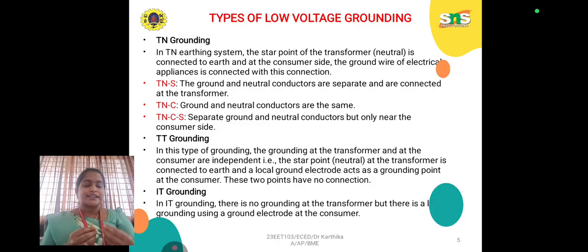Here TNS means the ground and neutral conductors are separate and are connected at the transformer side. TNC means ground and neutral conductors are the same. TNCS means separate ground and neutral conductors but only near the customer side, which means our house side. In TT grounding, the grounding at the transformer and at the consumer side are independent, like the star point. These two points have no connection. And in IT grounding, there is no grounding at the transformer, but there is a grounding connection using a ground electrode at the consumer point. Mainly three types of low voltage grounding are preferred: TN, TT and IT. And under TN we have types like TNC, TNS and TNCS.